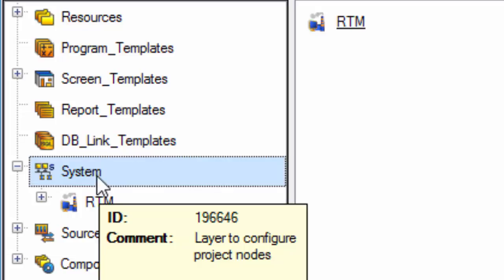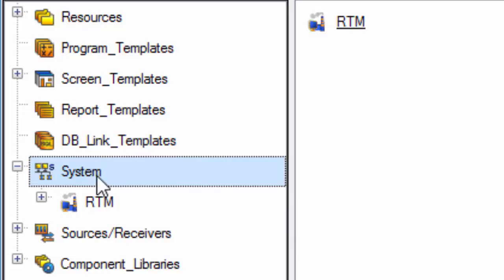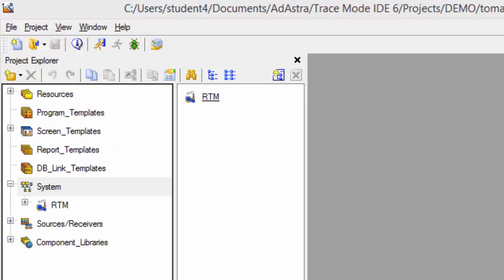Trace mode node determines the hardware platform. It may be a PC, programmable automation controller, tablet, or browser, on which the appropriate runtime trace mode must be running. The number of nodes in the trace mode project is limited to 10,000, and the communications between them can be based on all known types: network, Ethernet with a free topology, serial communications, point-to-point, multi-point, modem, dial-up, direct, radio, GSM, and others.